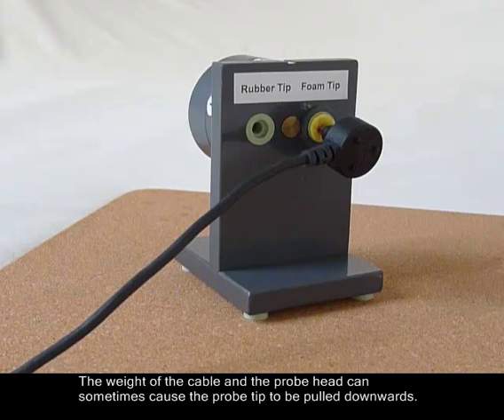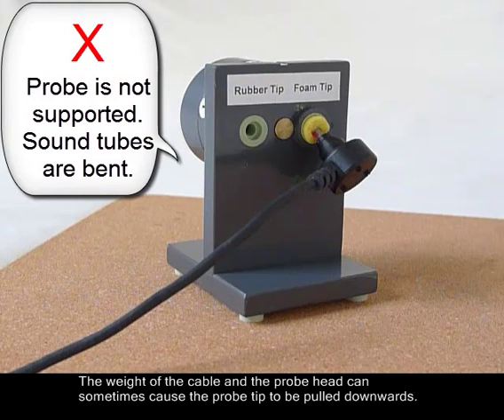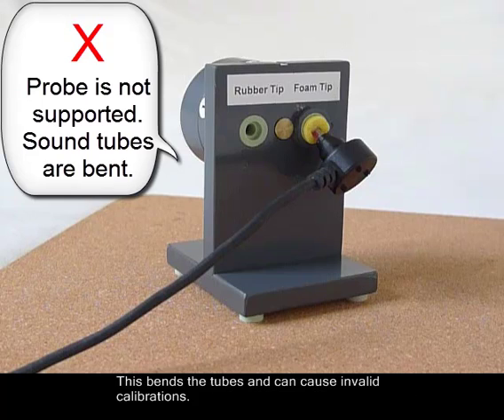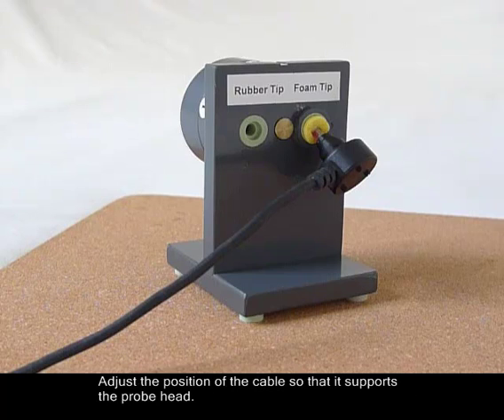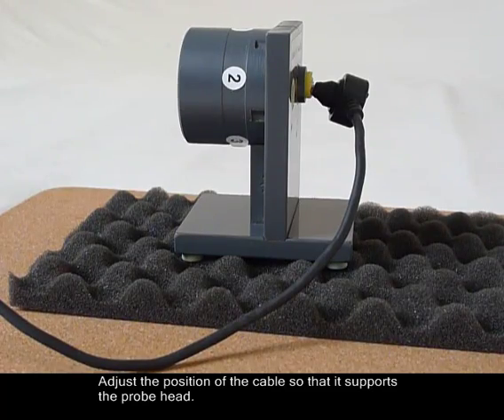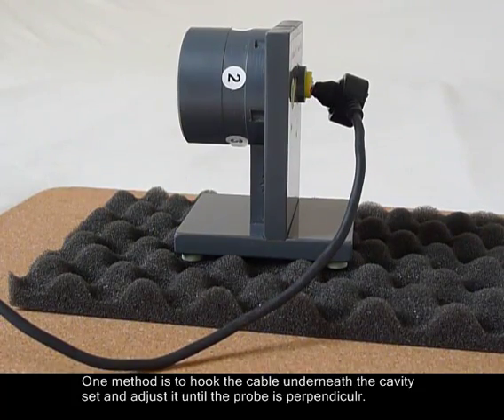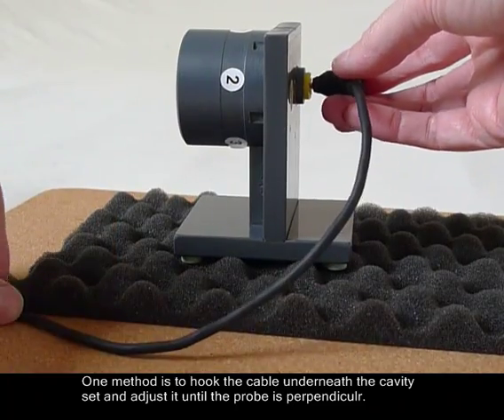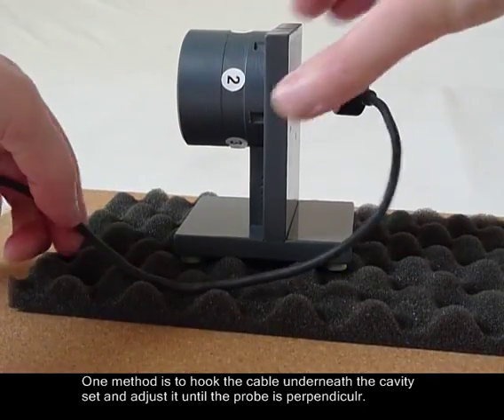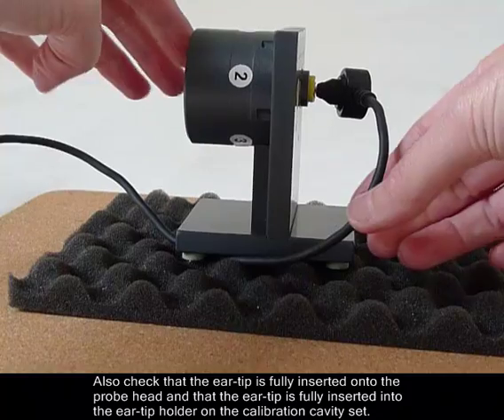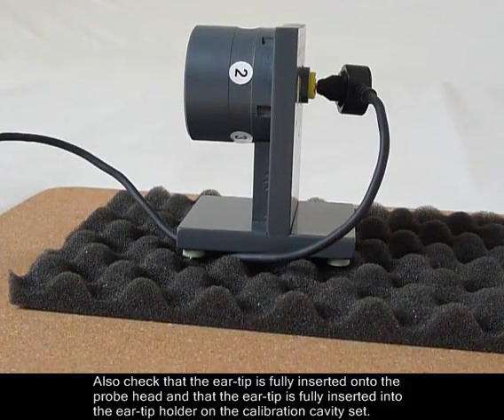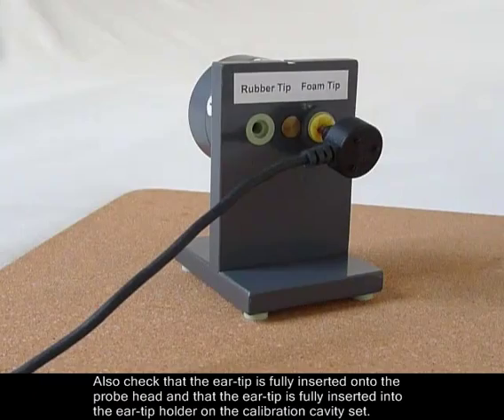The weight of the cable and the probe head can sometimes cause the probe tip to be pulled downwards. This bends the tubes and can cause invalid calibrations. Adjust the position of the cable so that it supports the probe head. One method is to hook the cable underneath the cavity set and adjust it until the probe is perpendicular. Also check that the ear tip is fully inserted into the probe head and that the ear tip is fully inserted into the ear tip holder on the calibration cavity set.